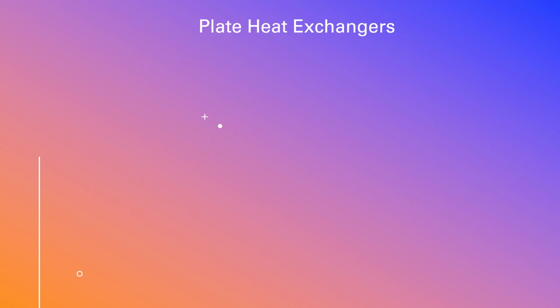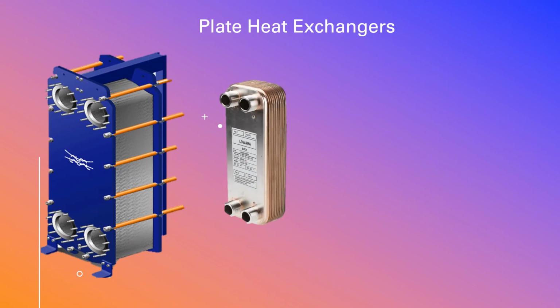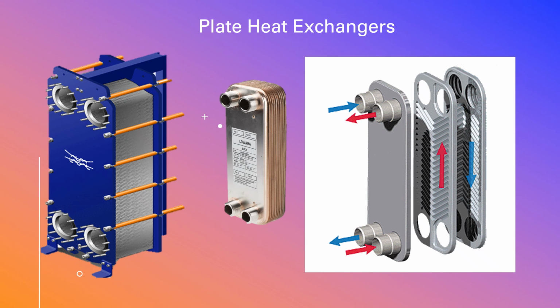So a quick look at plate heat exchangers. Here we have a couple of examples. We've got the stackable one where you can bolt the plates together and you can vary the amount of plates depending on what load you have. And we have a sealed brazed heat exchanger. Now, if you look at the diagram, you can see how they work. We have the cold liquid going in one side and coming out that side, and then the warm medium going in the other side, and they travel between the plates between each other and are very efficient.